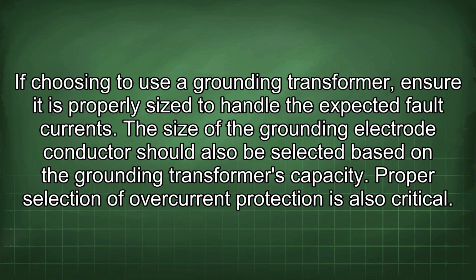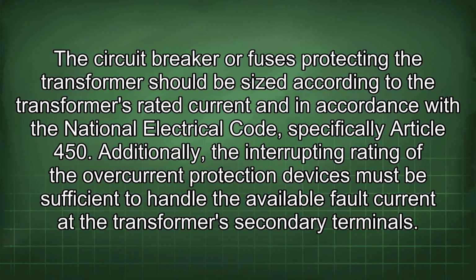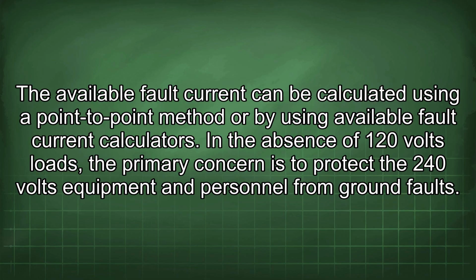Proper selection of overcurrent protection is also critical. The circuit breaker or fuses protecting the transformer should be sized according to the transformer's rated current and in accordance with the National Electrical Code, specifically Article 450. Additionally, the interrupting rating of the overcurrent protection devices must be sufficient to handle the available fault current at the transformer's secondary terminals. The available fault current can be calculated using a point-to-point method or by using available fault current calculators.